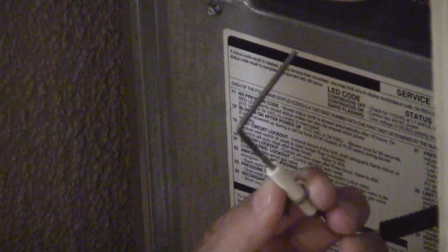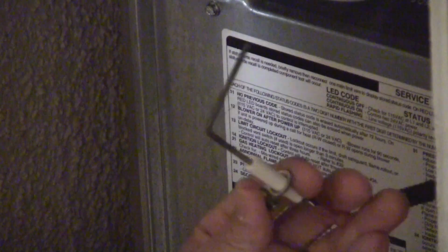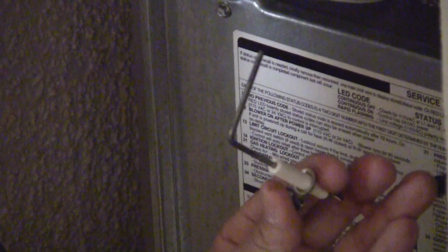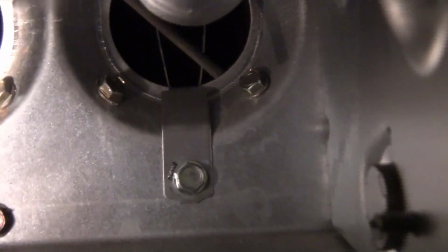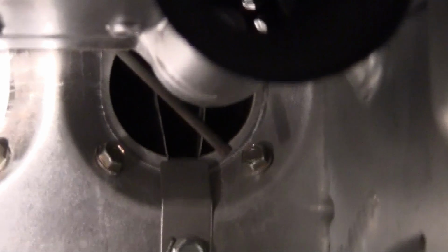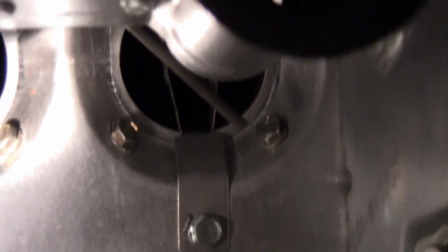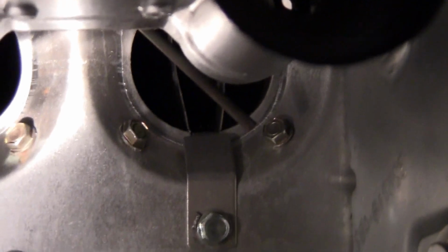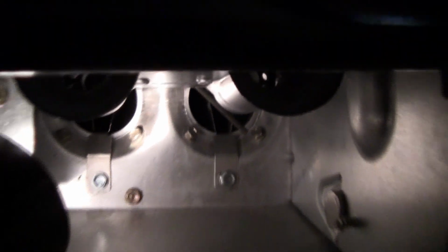So this is nice and clean now. Probably don't even need to do it, but I have a white paper towel here, and I'm just going to go ahead and wipe that down. And now I'm going to go ahead and put this back into the furnace. Okay, here is the flame sensor back inside of the furnace, held in. I got the hex head screw in there tight. The way that the sensor is located is just pointed not directly in the flame path. It's a little bit at the bottom, but that is still catching the flame, as before, and it worked fine. And we're going to go ahead and run the furnace right now.